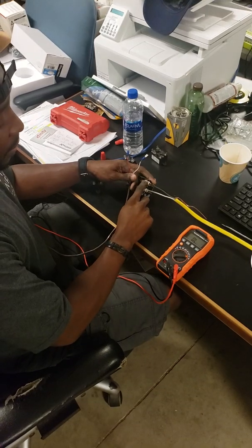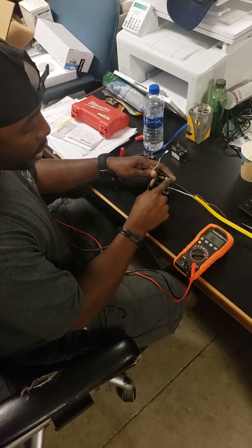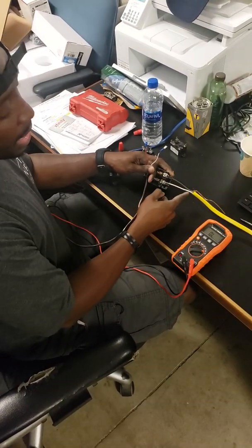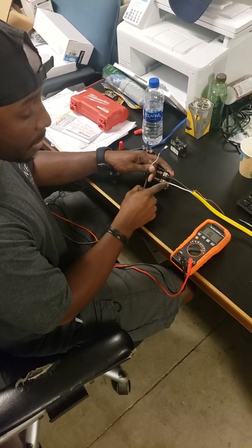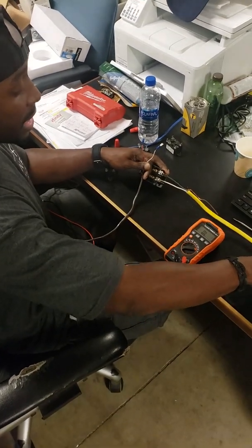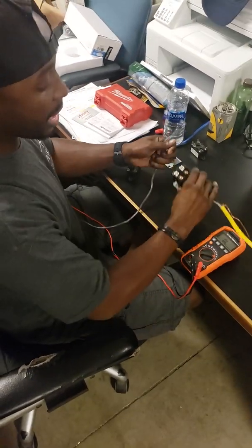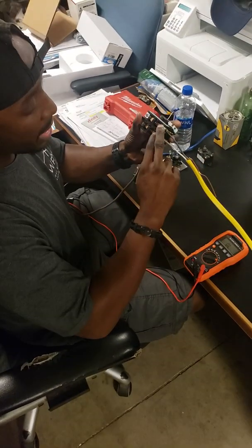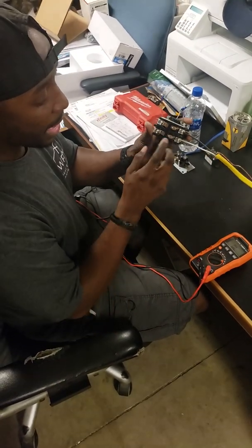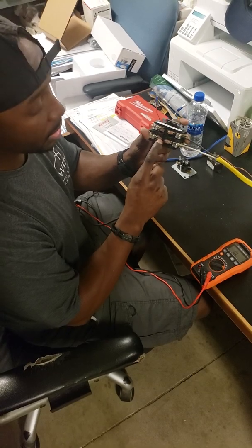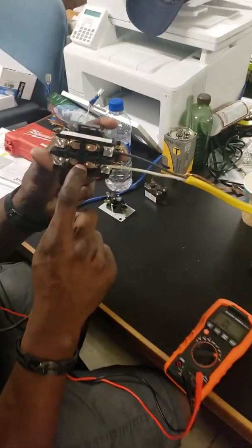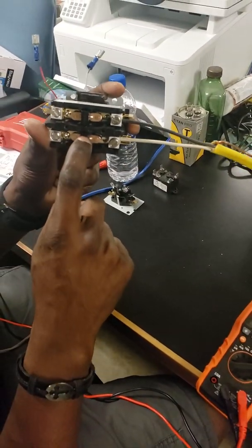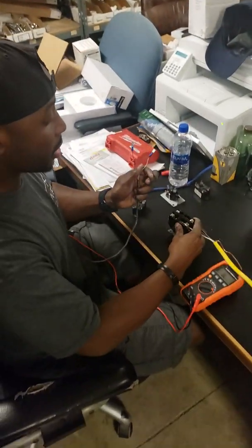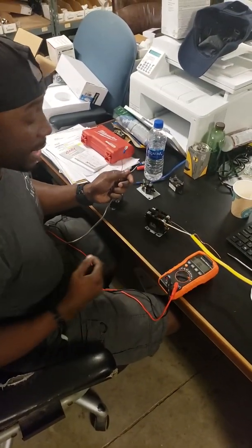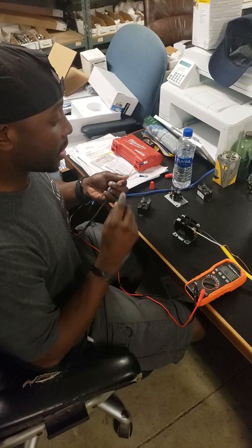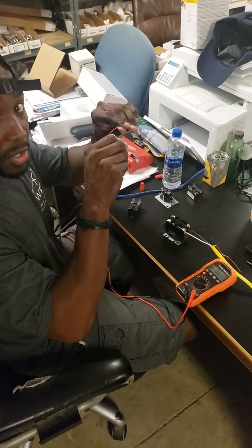This is a 240 volt circuit because 120 volts is coming in from this side, and 120 volts is also coming in from this side. And these are coming from the disconnect box. Now, this doesn't send voltage to this side unless that's pushed in. Why is that important? Because the thing that pushes that in is not your finger, of course. It is the 24 volts that comes off your transformer.